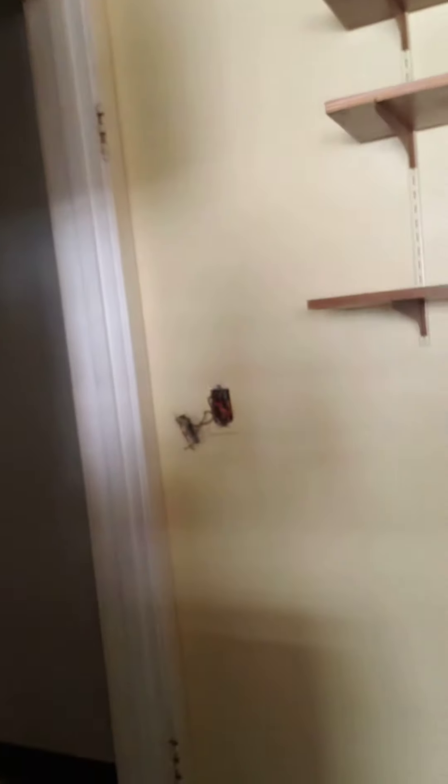They were using the green wire as a ground, but it's actually the light switch — and that was causing my overload. A lot of boxes were opened up over here, and also the living room ceiling light fixture had to be taken out.